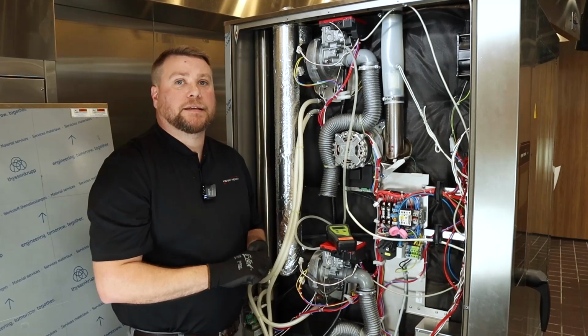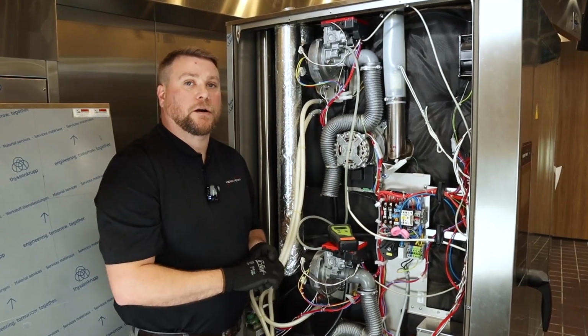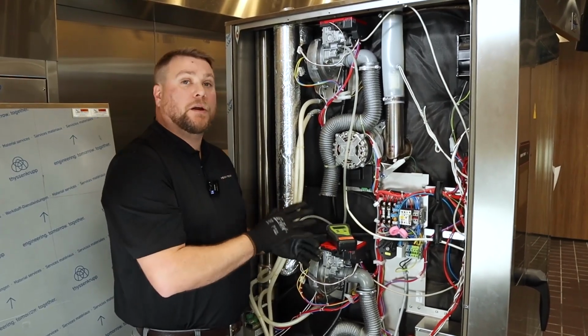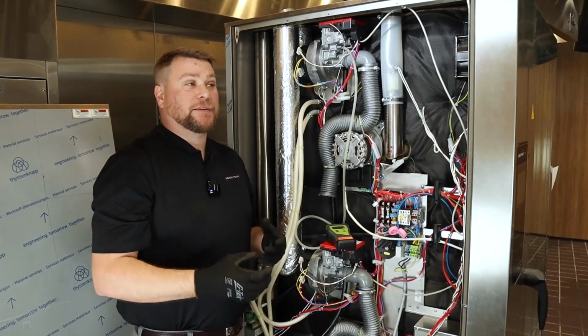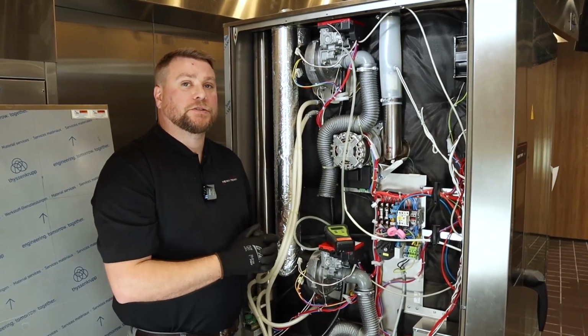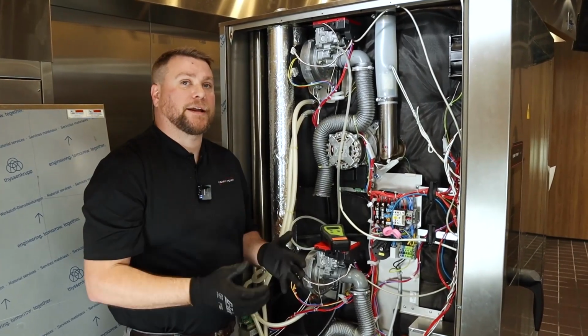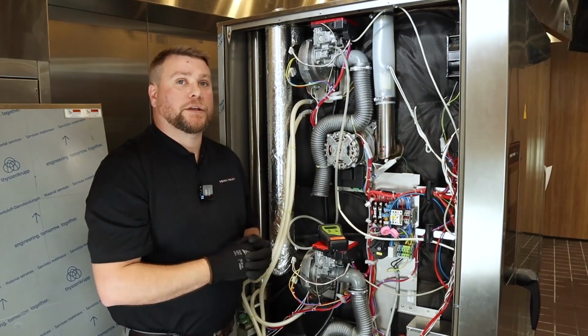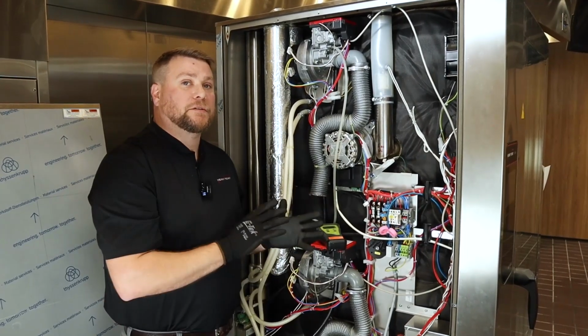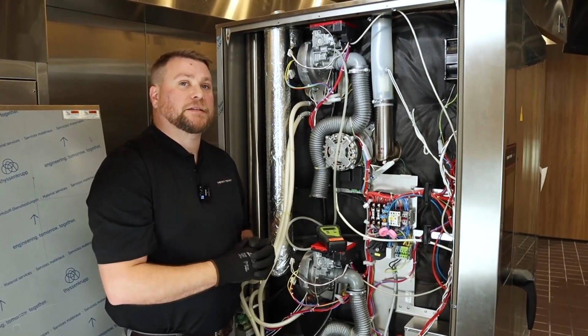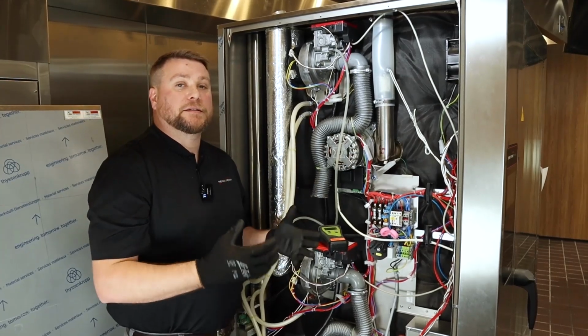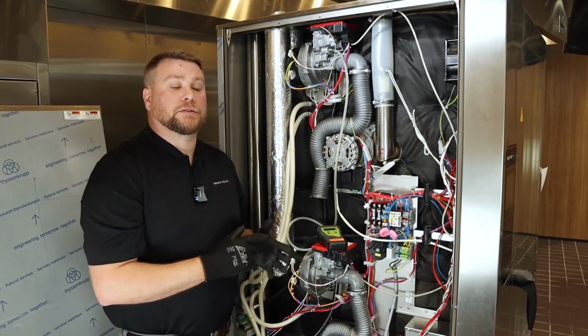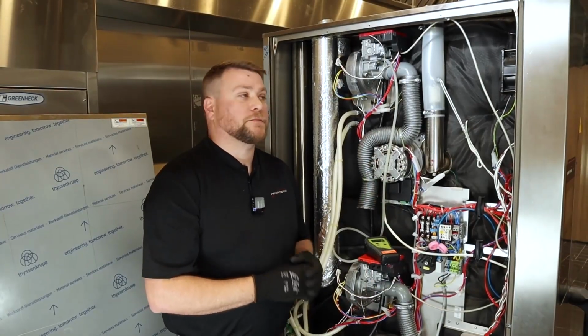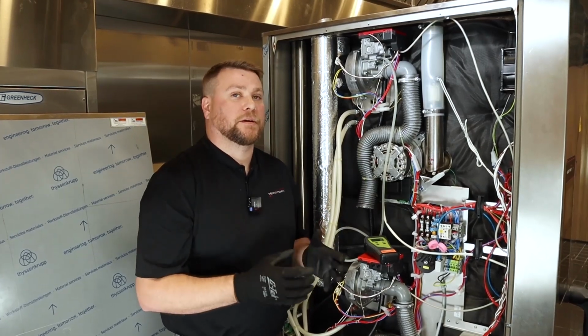Guys, if we are seeing above 20 inches of water column for natural gas in a store with gas pressure, because maybe they actually do have a volume issue, but the regulator has been cranked up so high that it's above 20 inches of water column, for Sam's Club stores, that unit needs to be taken out of service, and this needs to be communicated to the store. And this should help you in terms of troubleshooting gas issues when it comes to this problem.